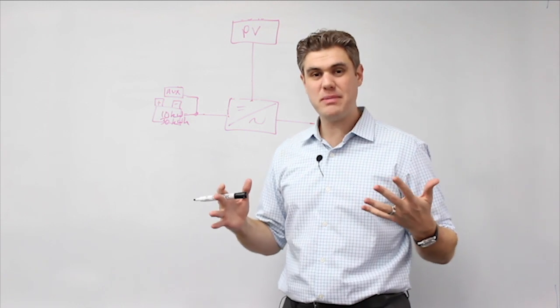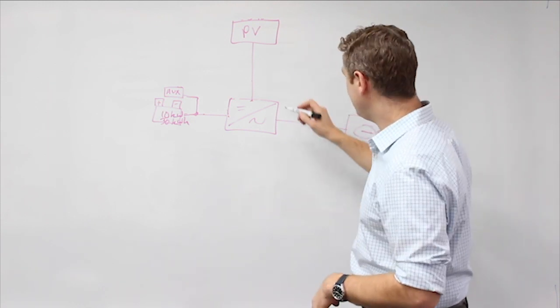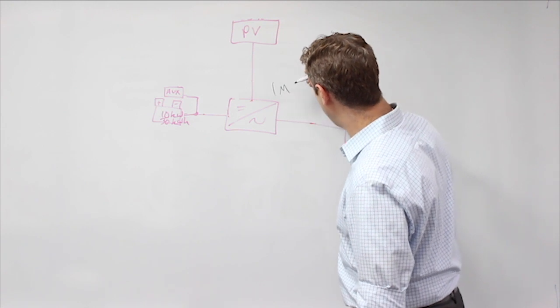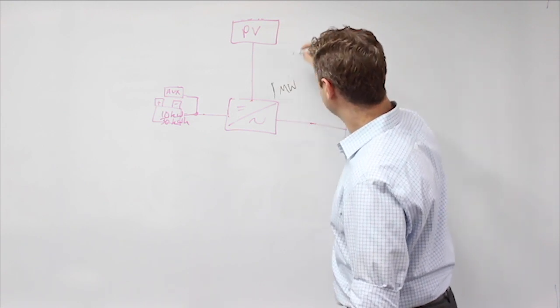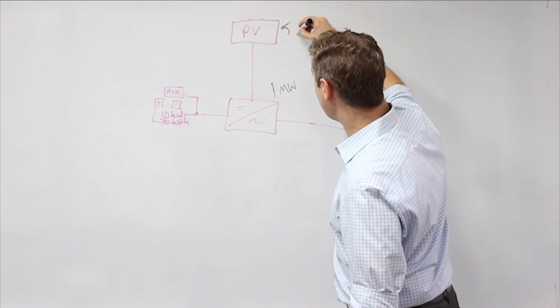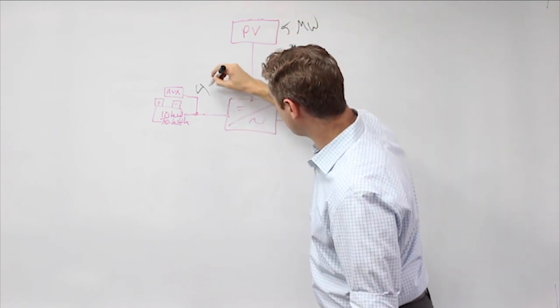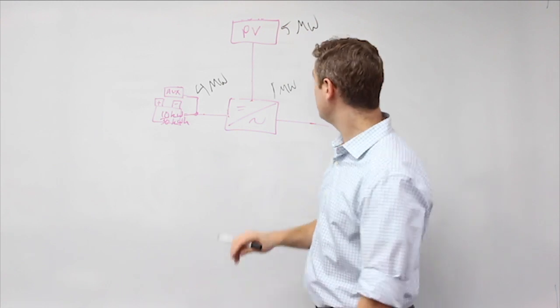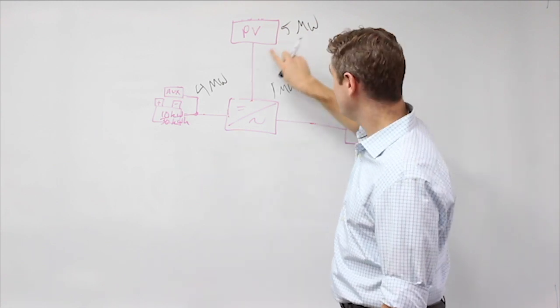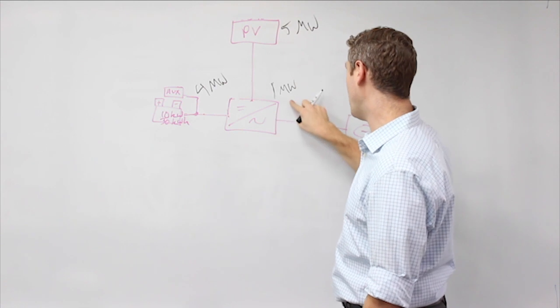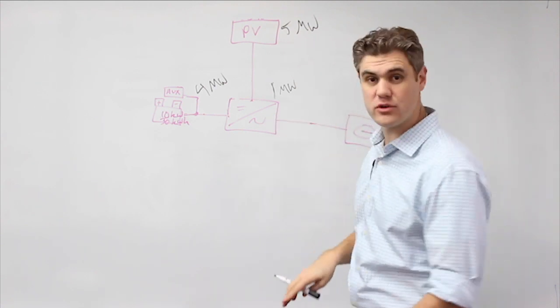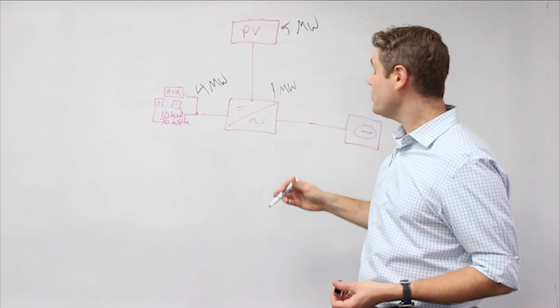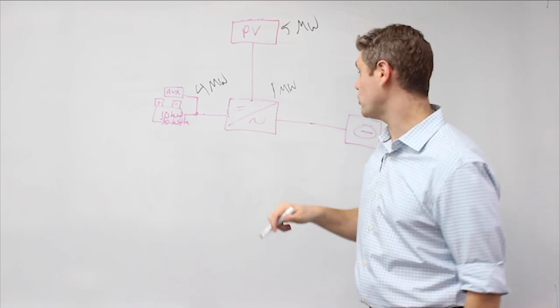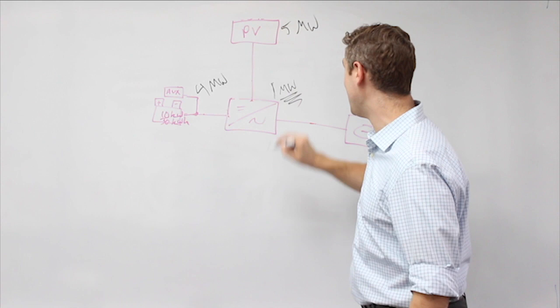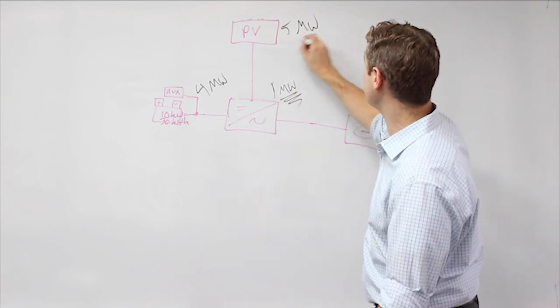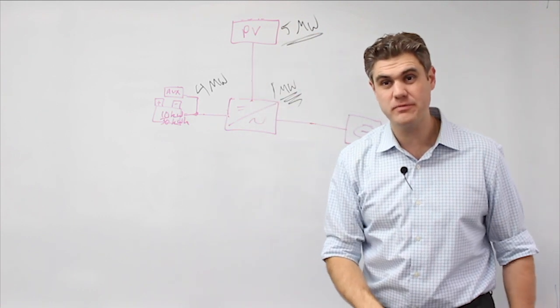So how does this impact us? Why is this important? Well, in a DC-coupled system, this could be 1 megawatt, but the solar could be 5 megawatts, and the battery could be 4, right? Why not? You could have 5 megawatts coming out of this guy, 4 of it could be redirected into the battery, while 1 ends up going out of this inverter over to the grid. The utilities companies' interconnection departments will rate this system as a 1 megawatt NEM system, even though you're giving the customer 5 megawatts of solar.